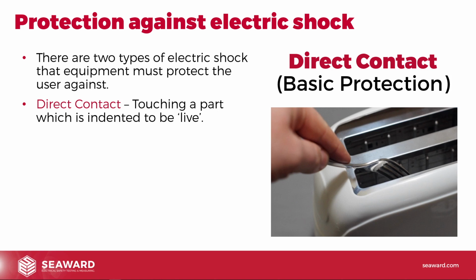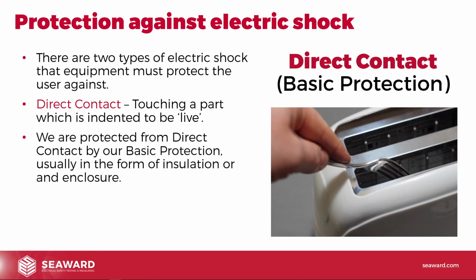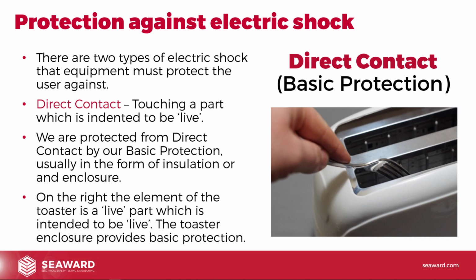In every piece of equipment, there will be parts that are designed to be live. For example, the conductors inside the cable are meant to be live. If we come into contact with those and get an electric shock, that is what we call a shock by direct contact. We're protected from direct contact by our basic protection. Usually this is in the form of insulation or the enclosure. So on the right, the element of the toaster is a live part, which is intended to be live. We want it to be live, so it'll toast our toast. The toaster's enclosure provides the basic protection.